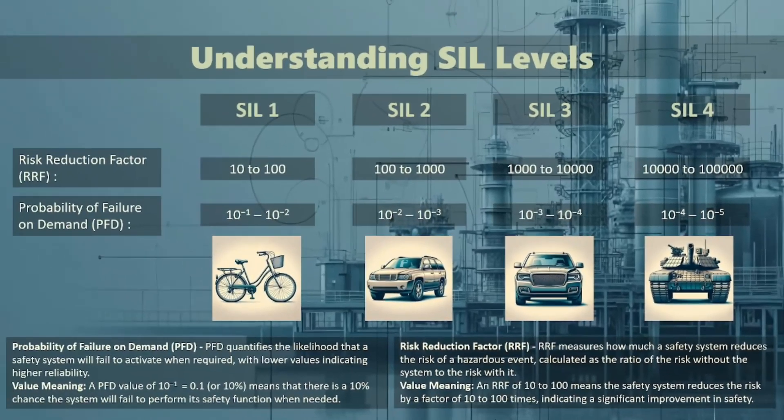SIL 1 is the entry-level safety, like a sturdy bicycle. It offers a risk reduction factor of 10 to 100, meaning it reduces risk by up to 90%. SIL 2 — think of this as your family car. It provides a moderate level of safety with an RRF of 100 to 1,000, reducing risk by up to 99.9%.